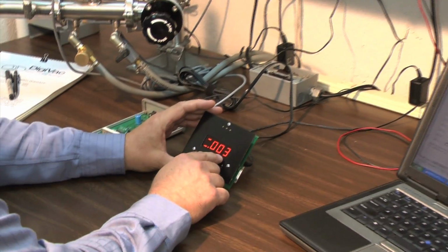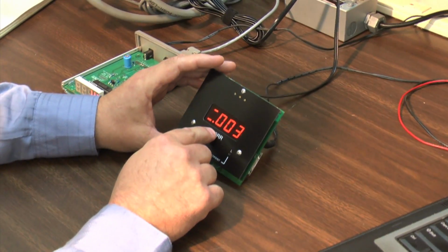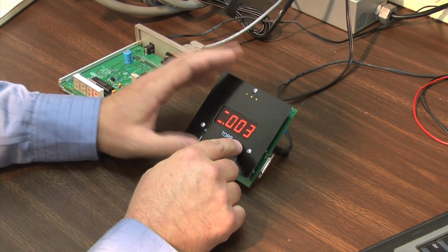Our 801W instrument is ready under vacuum. We can see it's given a good reading. It has 2 active set points. But of course, it's not properly calibrated compared to the reading on our convectron.